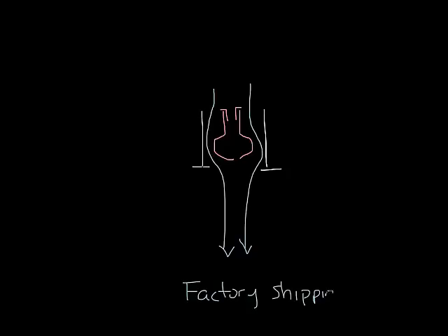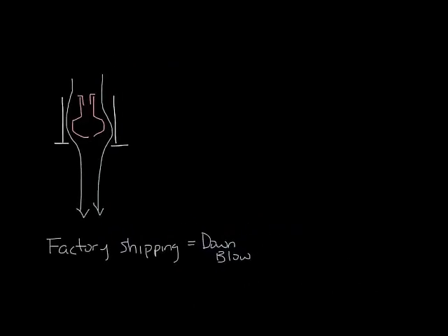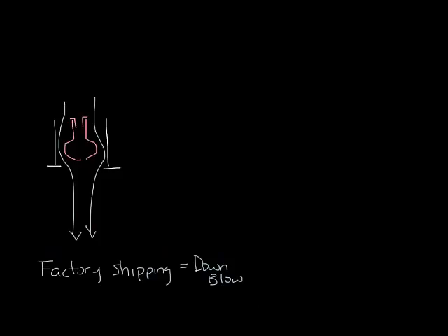Sadly, I would guess that many people don't adjust the pattern controllers from the way they ship from the factory. So now let's look at how they should be set. So let's move this over a little bit. In my case, we weren't on a perimeter, so we're looking at a cooling application, and it was pointed probably in the factory default straight down at me. So what you really want is for the air to be directed across the ceiling so it can roll the room and mix into the space without dumping on people.